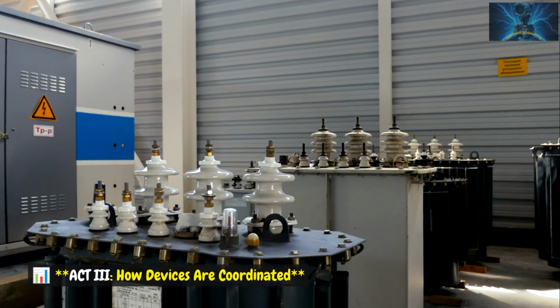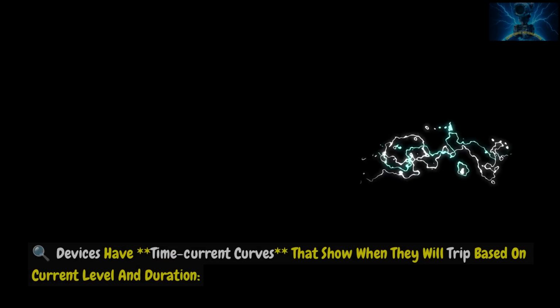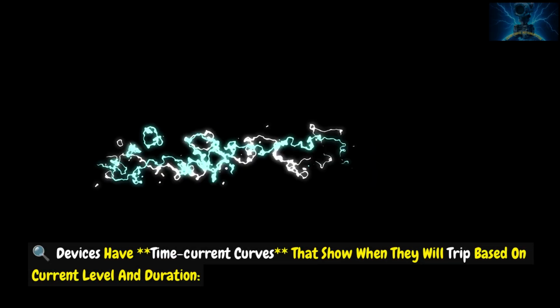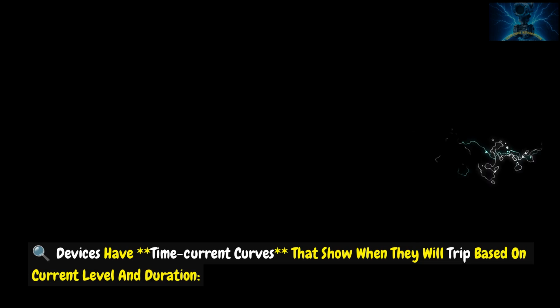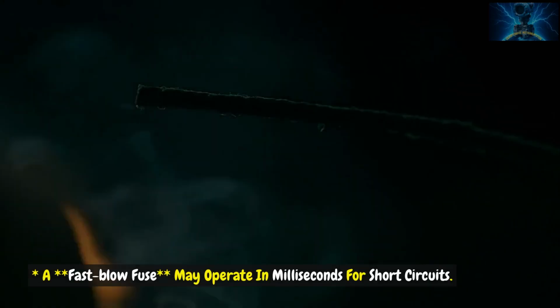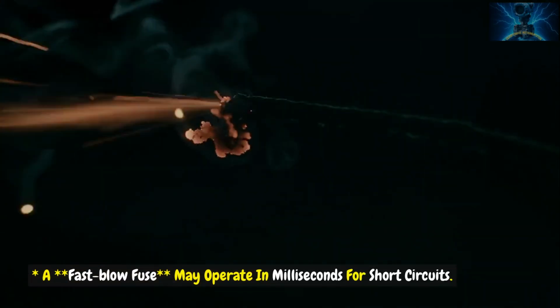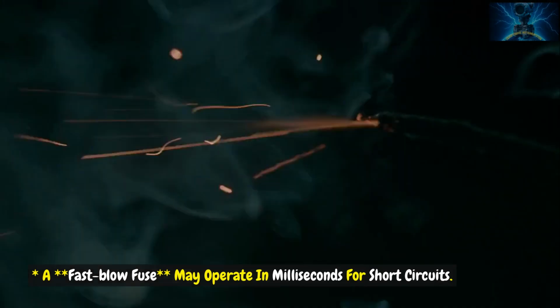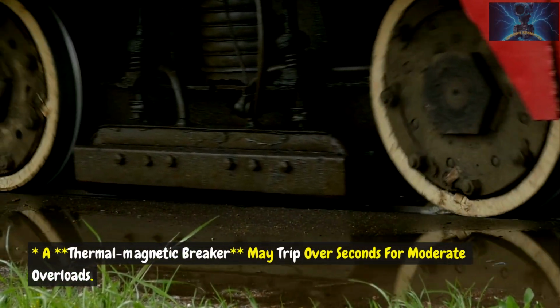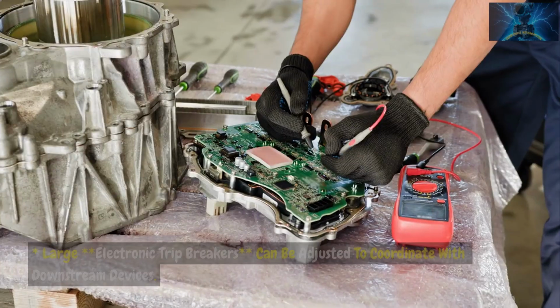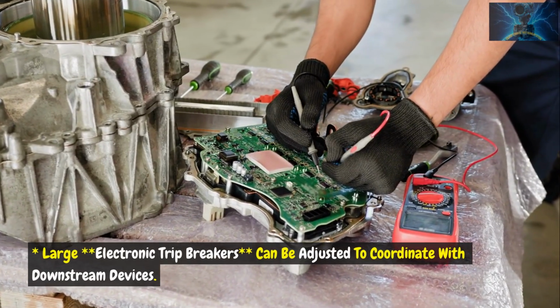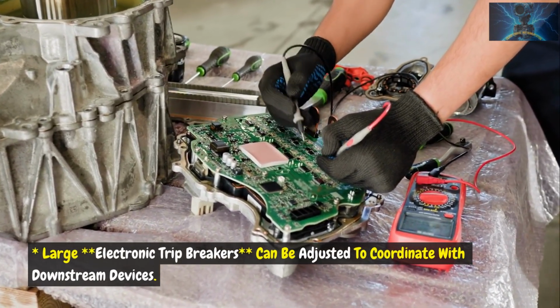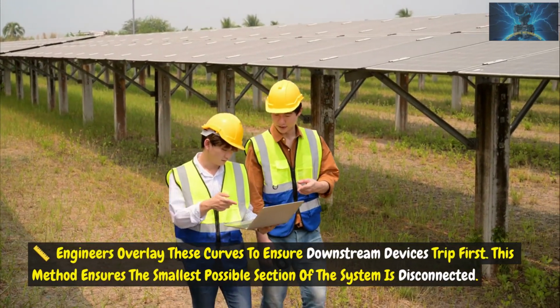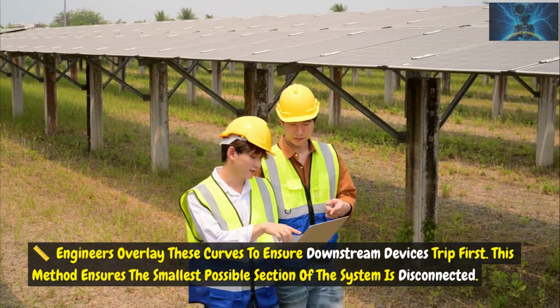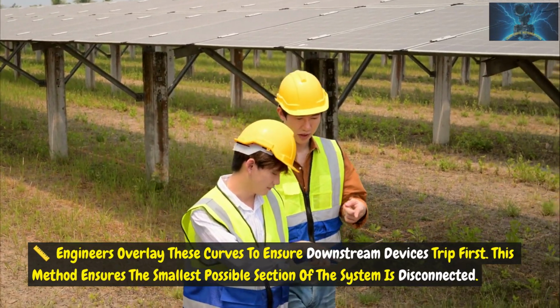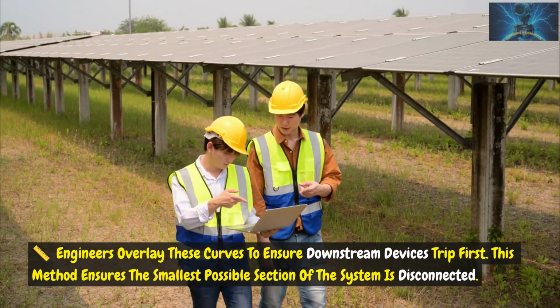Act 3. How devices are coordinated. Devices have time-current curves that show when they will trip based on current level and duration. A fast-blow fuse may operate in milliseconds for short circuits. A thermomagnetic breaker may trip over seconds for moderate overloads. Large electronic trip breakers can be adjusted to coordinate with downstream devices. Engineers overlay these curves to ensure downstream devices trip first. This method ensures the smallest possible section of the system is disconnected.